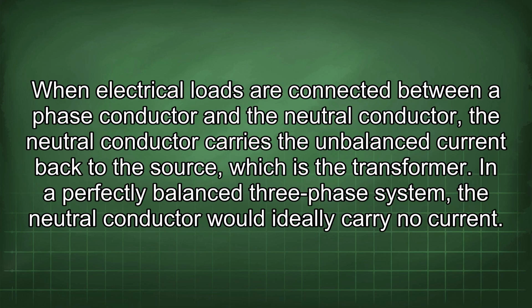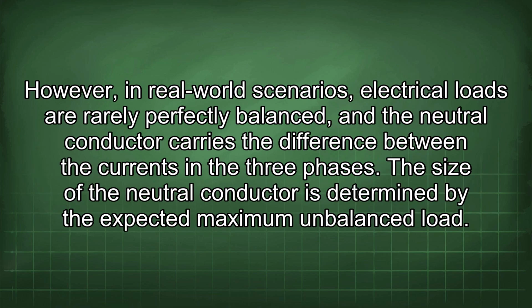When electrical loads are connected between a phase conductor and the neutral conductor, the neutral conductor carries the imbalanced current back to the source, which is the transformer. In a perfectly balanced three-phase system, the neutral conductor would ideally carry no current. However, in real-world scenarios, electrical loads are rarely perfectly balanced, and the neutral conductor carries the difference between the currents in the three phases. The size of the neutral conductor is determined by the expected maximum unbalanced load.